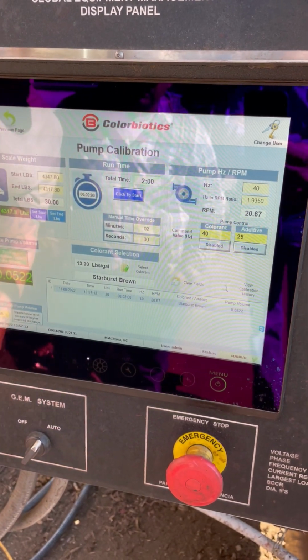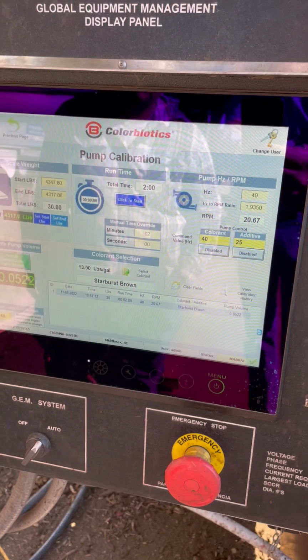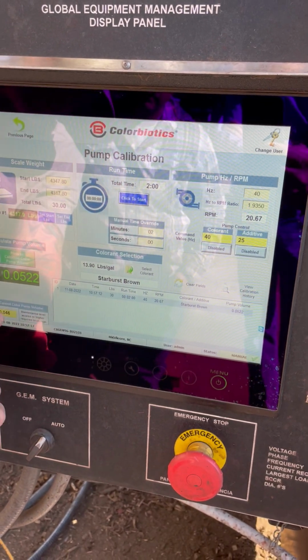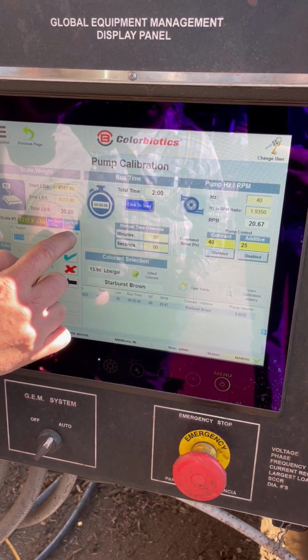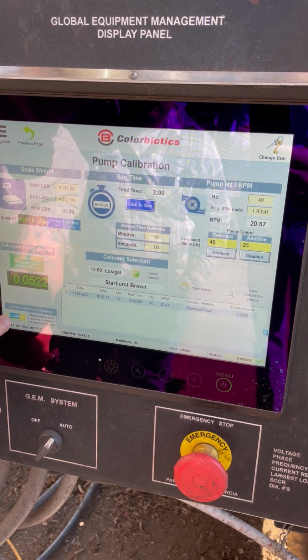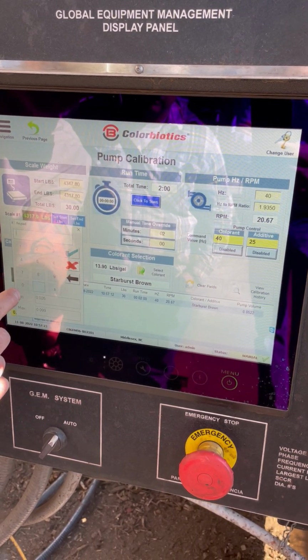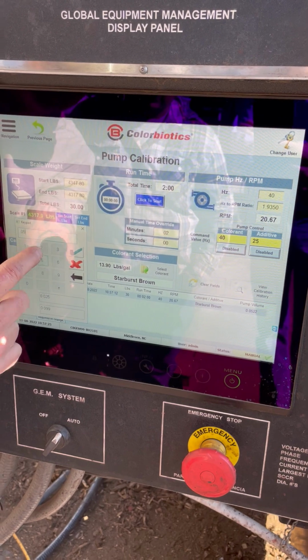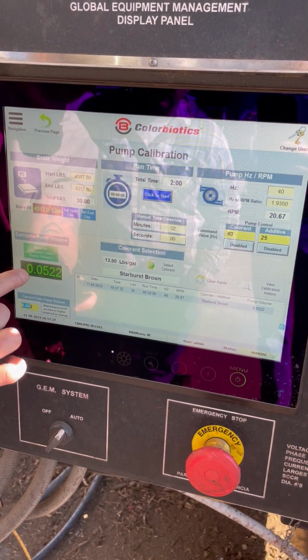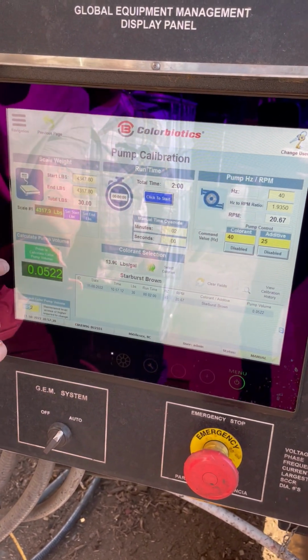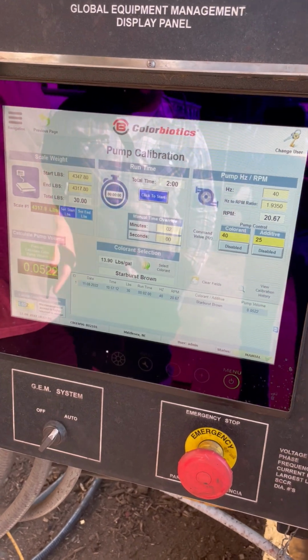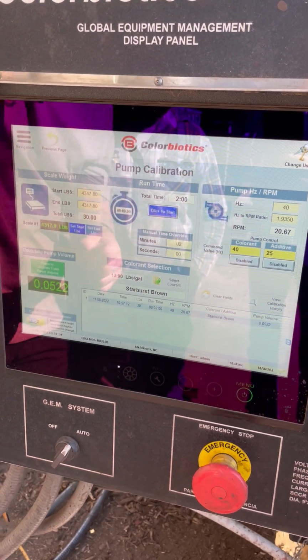So I press that, brand new hose, 0.052. I hit this, hold on, I hit that and I type in that 0.052. Always make sure you get that 0 in there, because if you go to 0.5, the pump is screaming and you guys are customer of the month.